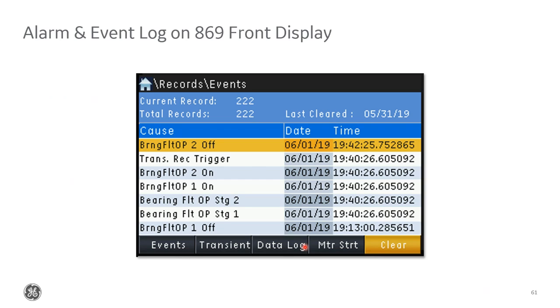So if a fault were to occur, you'd see an alarm directly on the relay's display. Here we're showing an example of the sequence of event recorder screen. You can see the bearing fault function picked up on its stage one warning, and then right after it picked up on stage two. And then after the set time delay, they both officially alarmed. So this message would look similar for the other categories. Instead of bearing, it would say something like stator fault or mechanical fault, but similar types of alarms. And this would directly pop up on your target screen as well.